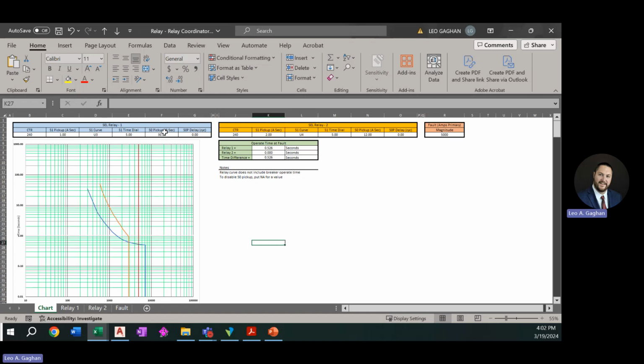We can see here both of our 50 and 51 pickups are in amps secondary. So if you wanted to convert that to amps primary, you just multiply times the CTR. Let's say I want to move this back over here. So right now we're operating instantaneously, or without delay, because nothing's instantaneous. If we wanted to put an intentional delay in here and make it a definite time overcurrent curve, we could do that. We can see that here. Let's put in a 30 cycle delay. That's half a second.